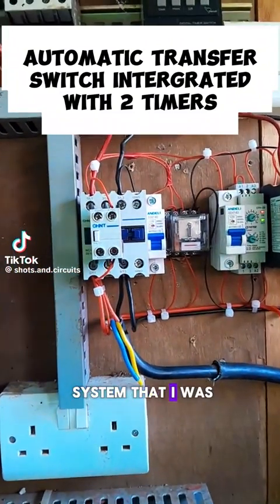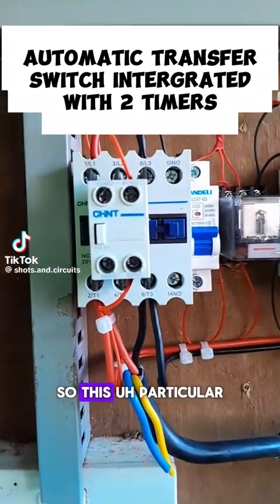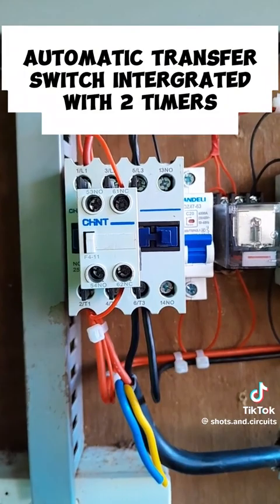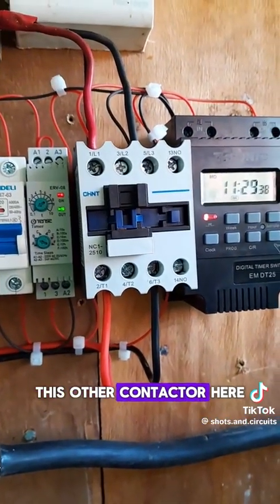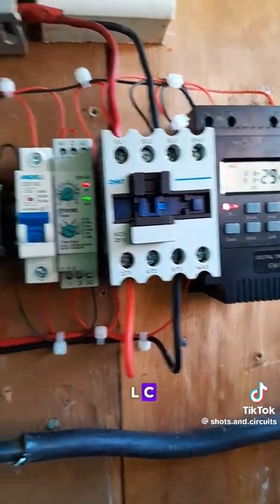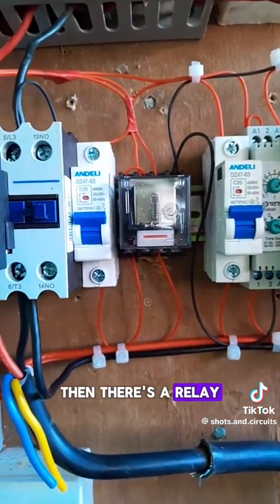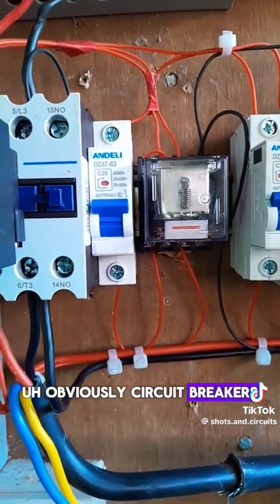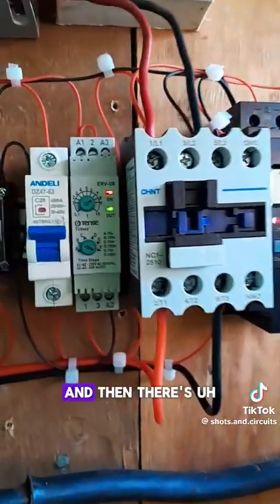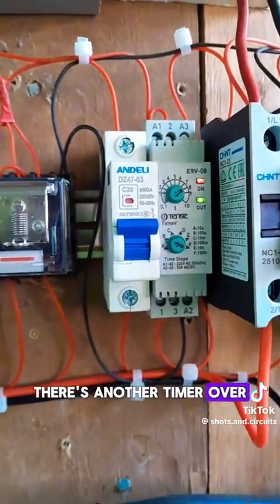So this is the system that I was telling you about. This particular contactor represents solar backup. This other contactor here represents KPLC. Then there is a relay, obviously circuit breakers or MCBs to control the power that goes into these controls, this contactor. And then there is another timer over here.